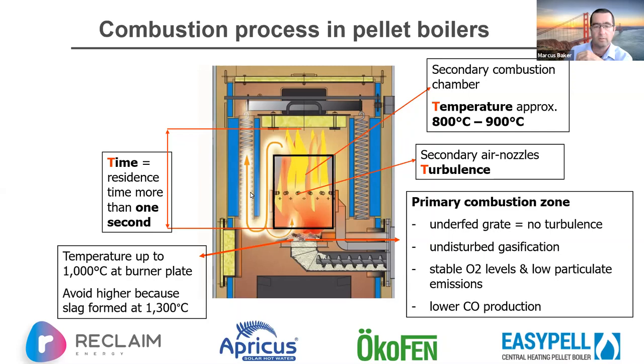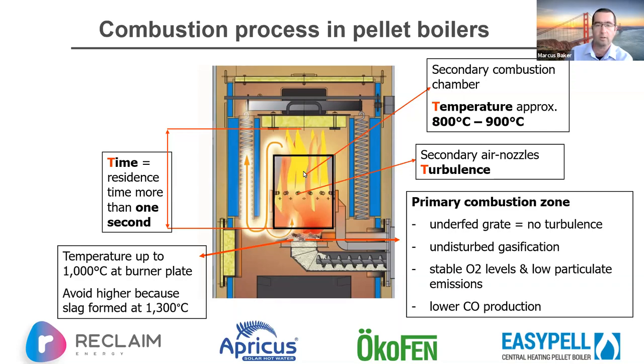Up here there's a lot of turbulence occurring because of the springs, and there are turbulators in the model — a common design. You get good heat exchange to the sides of the boiler water jacket, and a good dwell time. From the reversal point and back up again it's at least a second, and you'll see why that's important. We've got our three T's all occurring within the combustion zone.